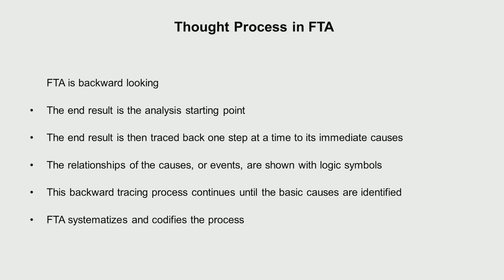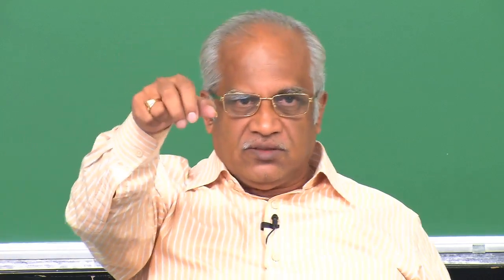Effectively it is a backward-looking approach. You put the pump trip at the end: it can happen because power is not there or the pump bearing is not working. If the pump bearing is not working, maybe the oil is not there for cooling or some other problem. If the power supply is not there, maybe the switch has not closed or there is no power supply. So we develop backward — the end result is the analysis starting point and we trace back. We have logic symbols because two faults happening together, or each individual fault, can lead to the event — so we have logic gates: OR gate, AND gate, and things like that.